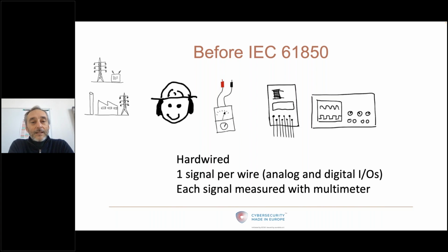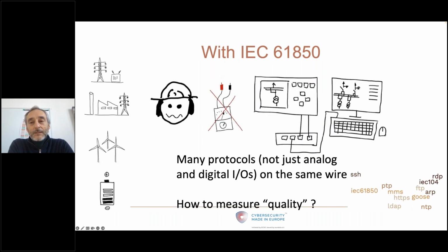Now if you look at the next slide, with 61850 everything is digitized and on a single wire, the Ethernet cable. All of the analog IOs and digital IOs, all the process values are on this single cable. But not only that, now there are other signals, everything needed to make this communication network work: time synchronization, the control plane of the network, authentication protocols like LDAP, and file transfer protocols to send configuration to the IEDs.